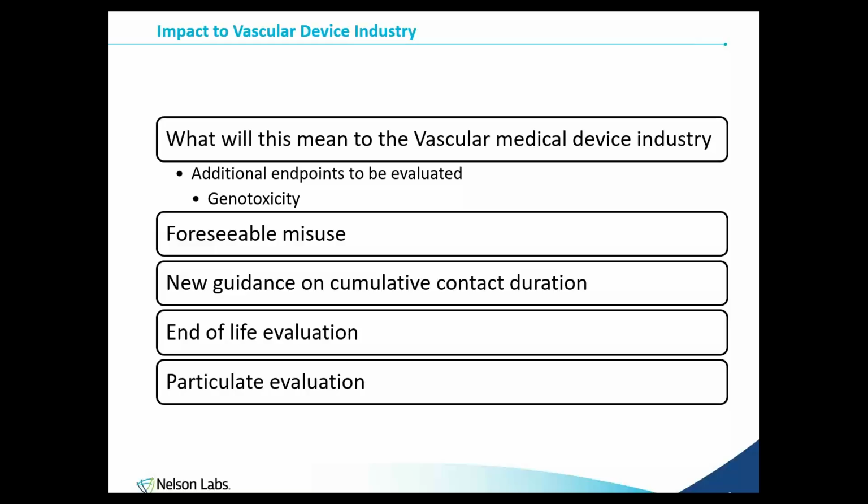Okay, so what does this update mean specifically to the vascular device industry? This is going to be impactful to almost all types of devices, but specifically looking at vascular medical products, the main impact is going to be an additional endpoint to be evaluated. Regardless of contact type to the body, vascular products will have to look at genotoxicity. We'll talk a little bit more about that in a second.